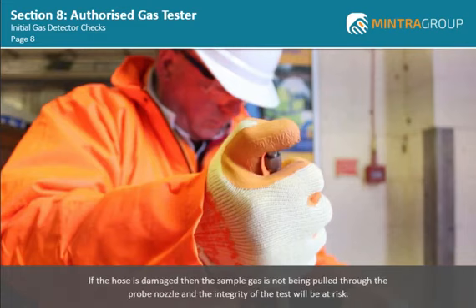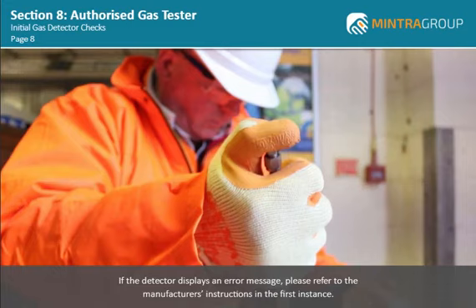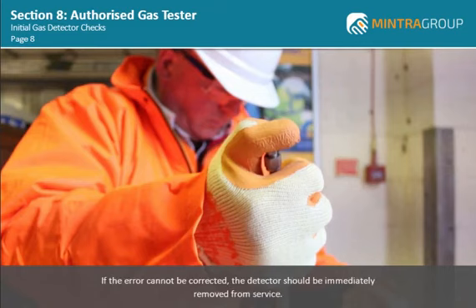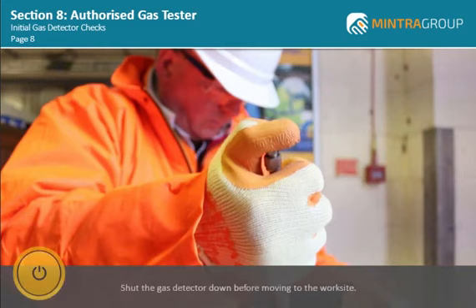If the hose is damaged, then the sample gas is not being pulled through the probe nozzle, and the integrity of the test will be at risk. If the detector displays an error message, please refer to the manufacturer's instructions in the first instance. If the error cannot be corrected, the detector should be immediately removed from service. When you're satisfied that the detector is working correctly, shut the gas detector down before moving to the worksite.